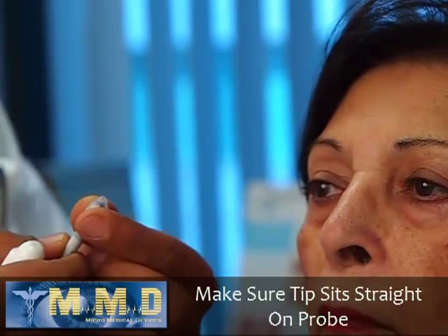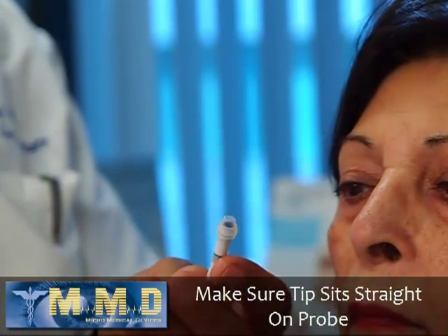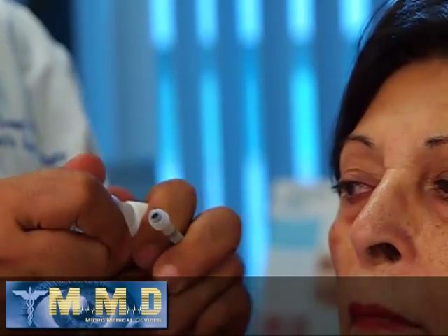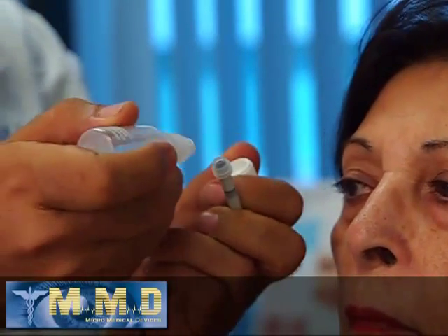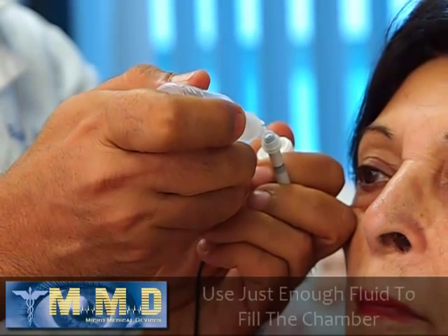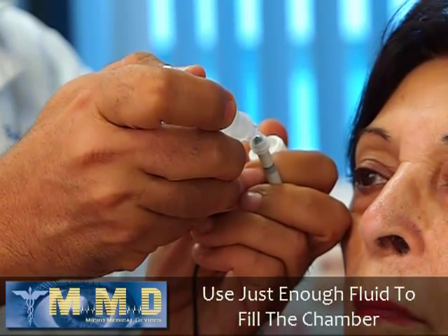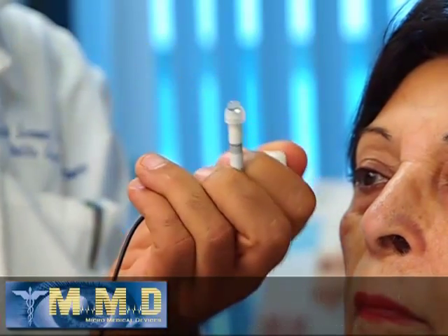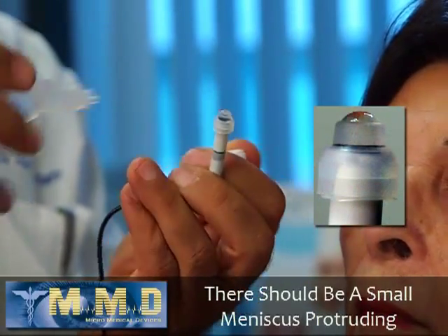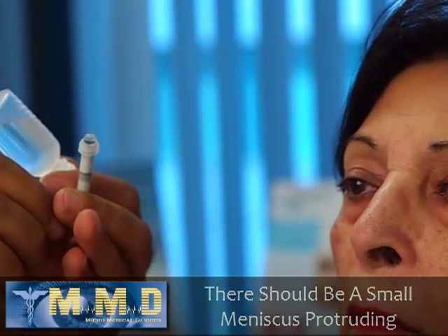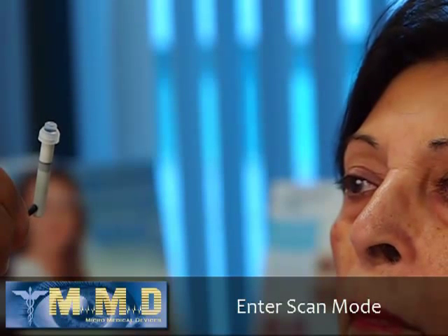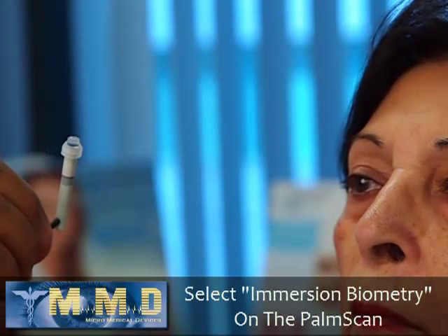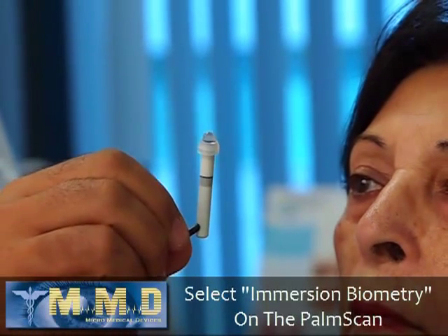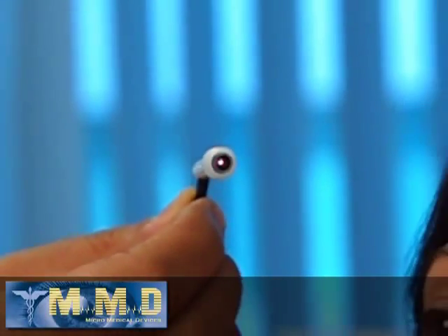So first, what I like to do is fill the Easy Immersion Tip with BSS, and to do that, I just tilt the Easy Immersion Tip and place just enough fluid to fill the chamber and a little meniscus of water on top. Now I'm ready to start the scan by going into the scan mode, A-Scan, and make sure that immersion biometry is selected. And as you can see, there is a blinking red light.